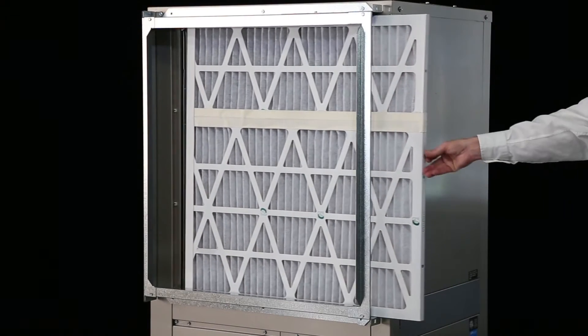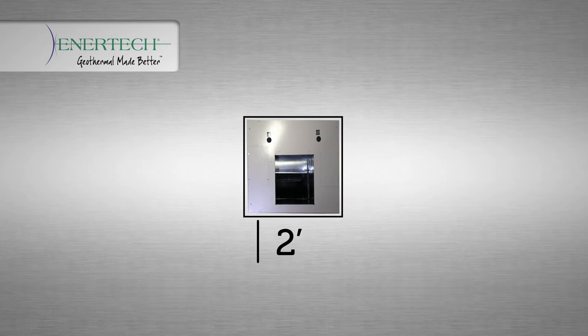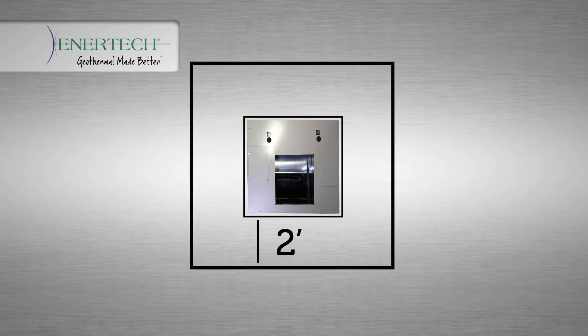It is important to allow adequate service access. A general rule of thumb is at least two feet in the front and two feet on at least one side. An optimum installation would allow at least two feet on all sides.